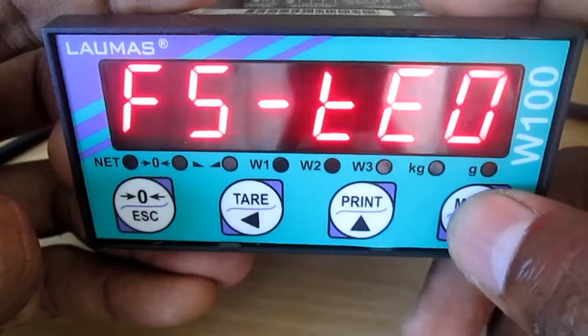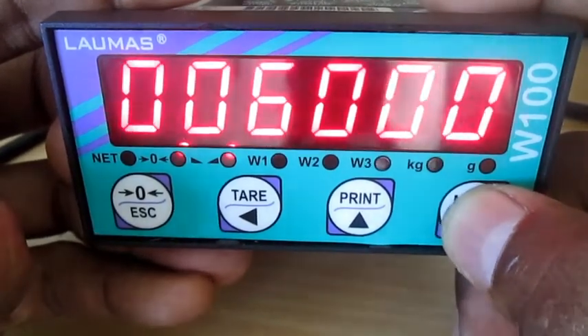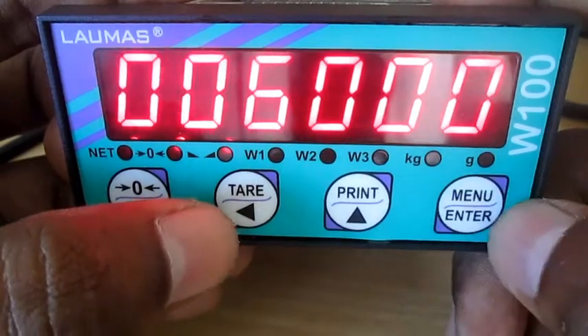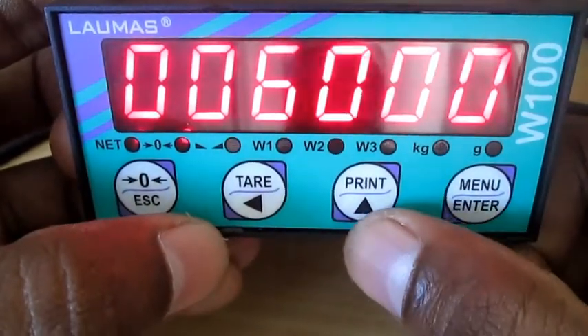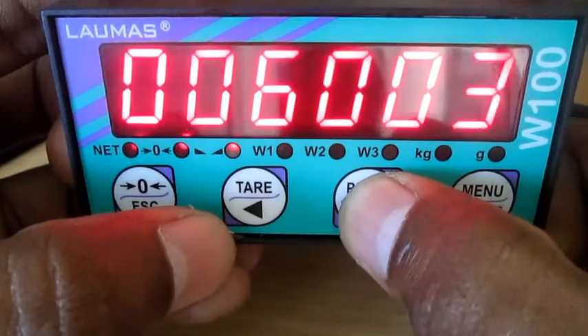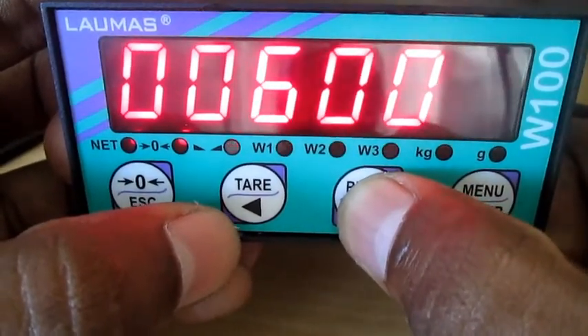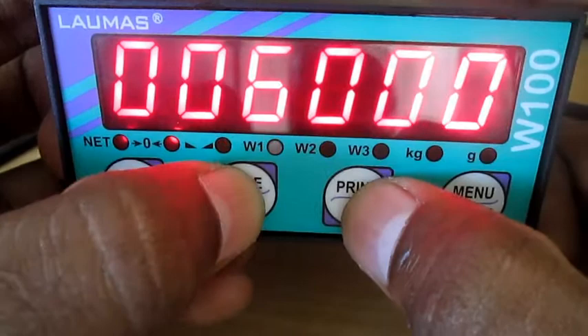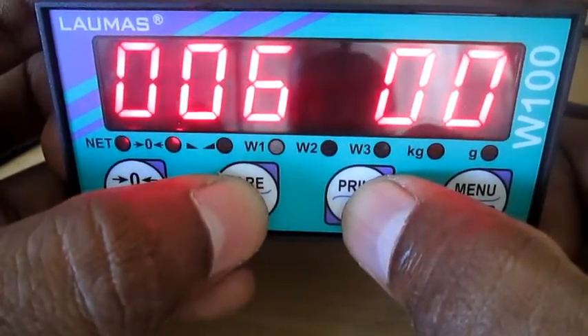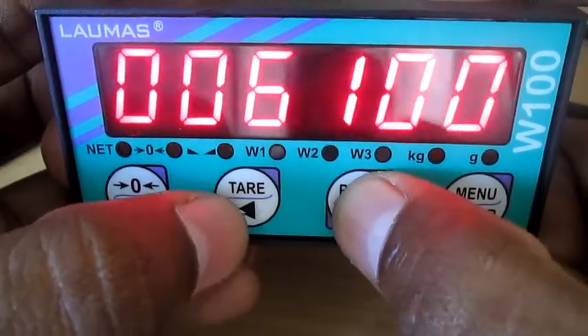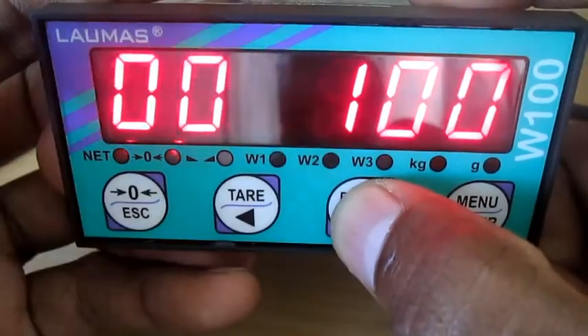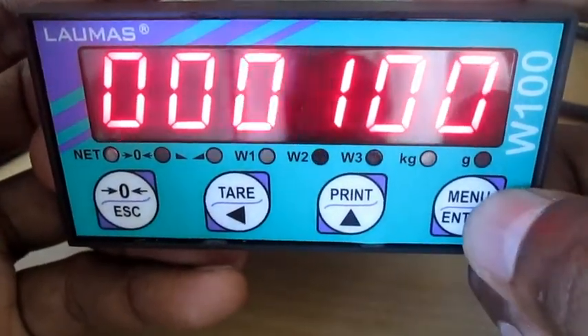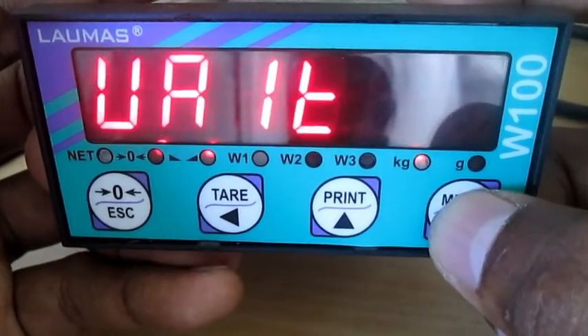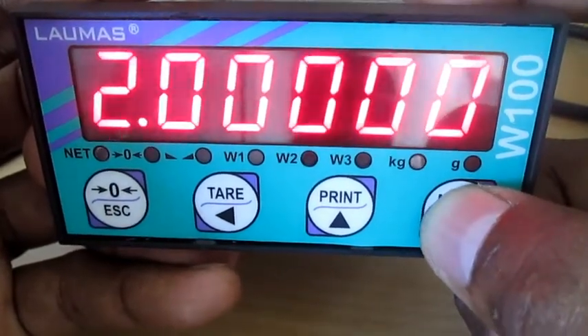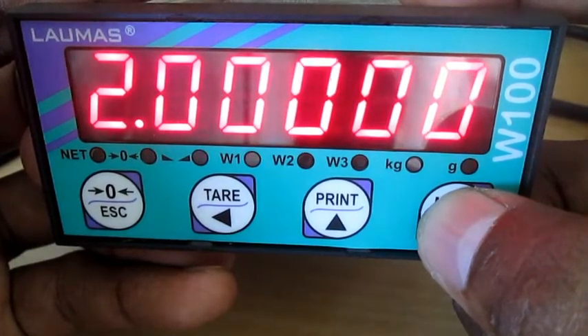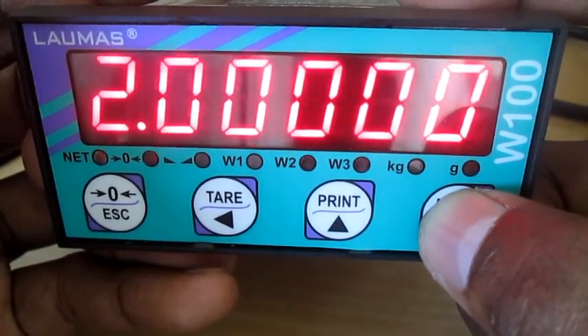Full scale display reads full scale theoretical value. Now we are going to set 100 kg using print button for increasing and decreasing the digits, TARE button for shifting the digit from right to left. Now we have set 100 kg, and then we are going to set sensitivity of the load cell. Default is 2.000.